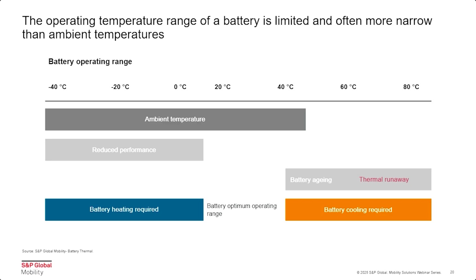When we talk about battery operation, it's important to understand that the optimal temperature range of a battery is quite narrow, often narrower than the surrounding ambient temperatures. This means there are scenarios where battery heating might be needed and scenarios where battery cooling might be needed, essential for maintaining the battery's performance. In extreme cases, ambient temperature around the world can fluctuate anywhere from minus 40 degrees to over 40 degrees. I hope none of you are in any of those climates, but it's possible.